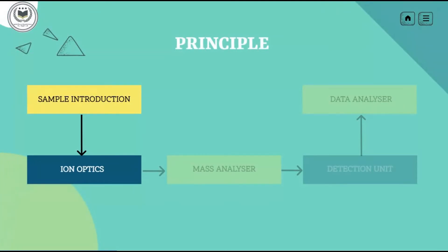Then comes ion optics. The set of electrostatic lenses located behind the skimmer cone is collectively referred to as ion optics. The role of the ion optics system is to guide the ion beam toward the mass analyzer and to prevent photons and other neutral species, such as non-ionized matrix components, from reaching the detector. The ion optics usually prevent this by positioning a photon stop or shadow stop in the ion path, or by guiding the ion beam off-axis.